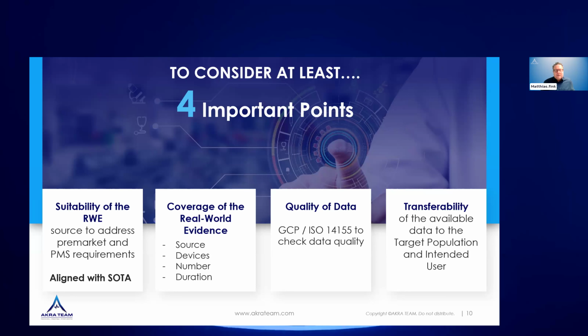So you have to make sure that the registry or the health record, whatever you're using, provides you that output that you're going to need to be aligned with your own clinical evaluation. You have to make sure to cover the devices, the number of devices, the duration, especially for long-term implants. Notified bodies expect that we provide the clinical data over the lifetime of the device. So you have to make sure these real-world data sources are not just, let's say, if you have a heart valve, usually notified bodies expect up to 10 years of data and follow-up at some point. So you have to make sure you're not going to stop collecting data after 1 year.